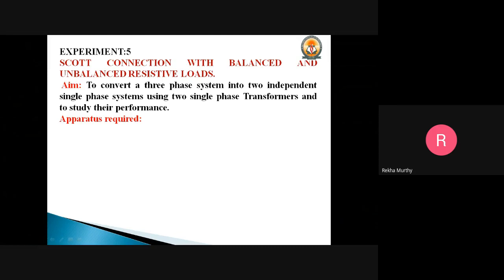The number of turns we take will be around 0.866 times the respective turns of the main transformer, in the case of the teaser transformer. So for the teaser transformer's primary side, we should take an 86.6% tapping. One end of both the primary and secondary of the teaser transformer will be connected to the center tap on the primary and secondary of the main transformer respectively.